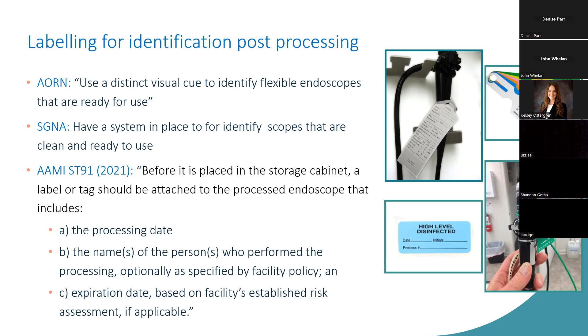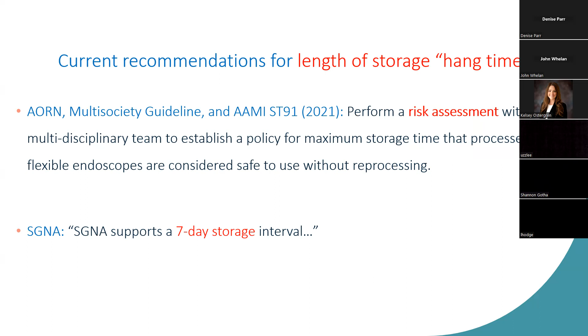So here in 2024, hang time is still variable. SGNA is the only organization still prescribing a certain number of days for hang time, 7 days, and they've done that for years based on a 2015 research study. All the other organizations reference basing hang time on a multidisciplinary risk assessment. We earlier referenced the need to pay attention to the FDA safety communications. A significant example from 2015 addressed supplemental reprocessing measures for duodenoscopes. This is when they were giving guidance on the heels of what was happening with CRE contamination. So they referenced at this point microbiological culturing, ETO sterilization, use of liquid chemical sterilant processing systems, or repeat HLD.